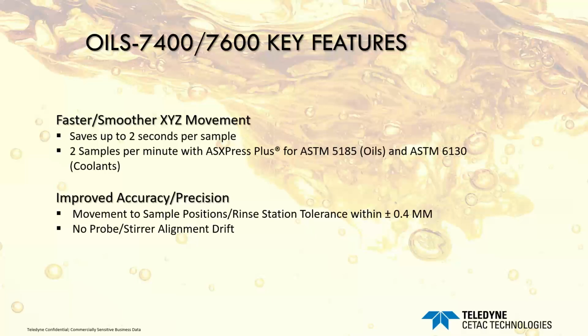All right, and then the Oils are awesome because they also have fast and smooth movement, and that movement translates into a savings of up to 2 seconds per sample compared to their predecessors, the ASX 1400 and ASX 1600. And the mechanics allow very precise movements. Now, how precise? Movement to the sample positions and rinse stations is kept within a tolerance of plus or minus 0.4 millimeters. The probe and stirrer are linked in a manner that you never have to worry about them drifting out of alignment. They will always be aligned with each other.